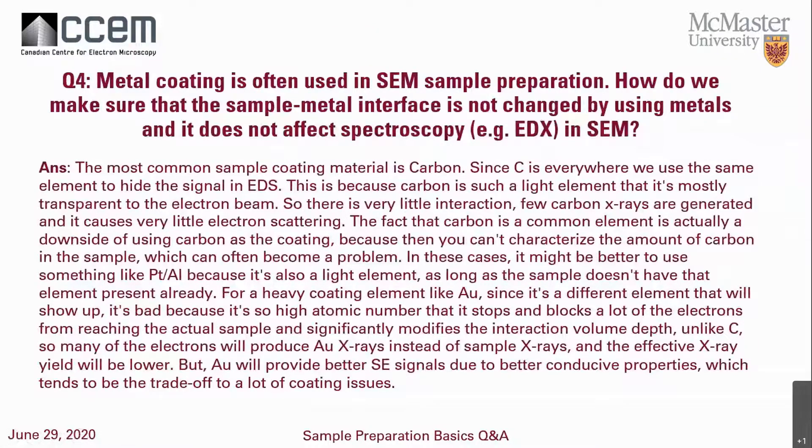Question four: metal coating is often used for SEM sample preparation — how do we make sure the sample-metal interface is not changed by the coating and doesn't affect the EDS spectroscopy? The most common sample coating material is carbon. Since carbon is everywhere, we use the same element to hide out the signal in EDS. Carbon is mostly transparent to the electron beam — very few carbon x-rays are generated and it causes very little electron scattering. However, the fact that carbon is a common element is a downside: you can't characterize the amount of carbon in your sample, so be careful if you're looking for carbon.